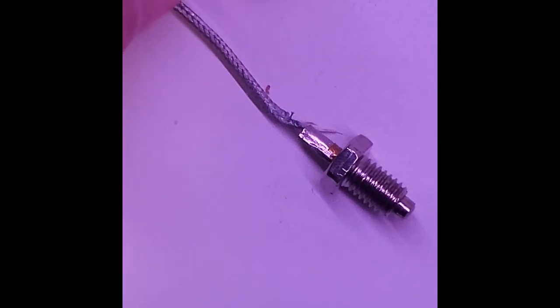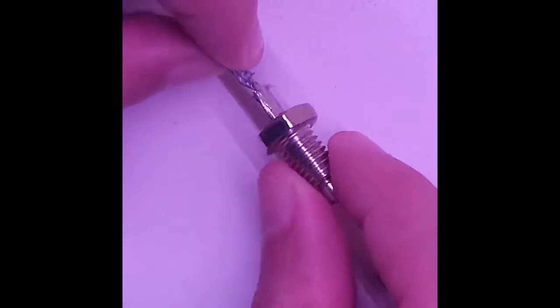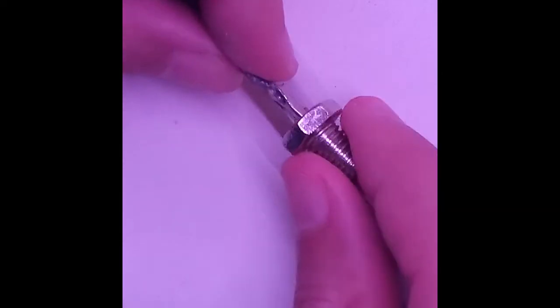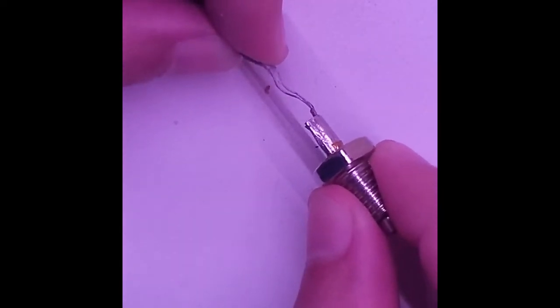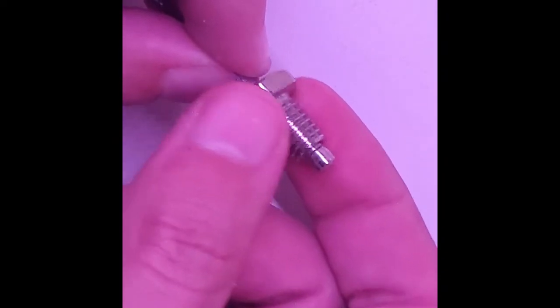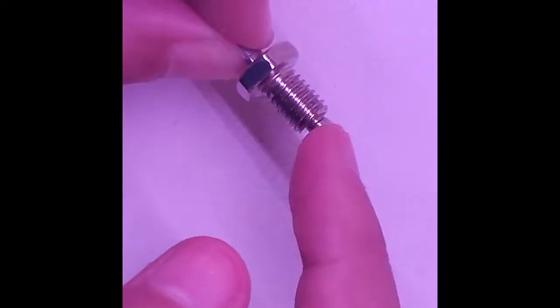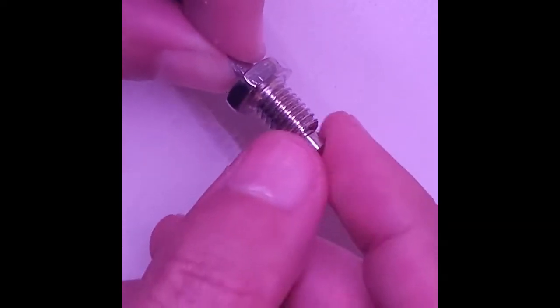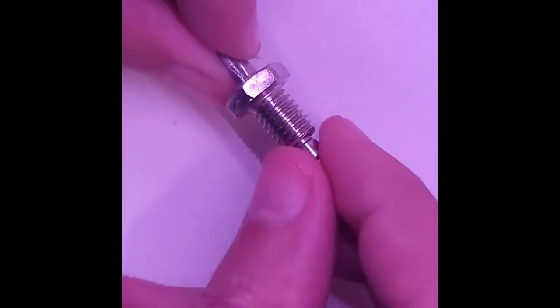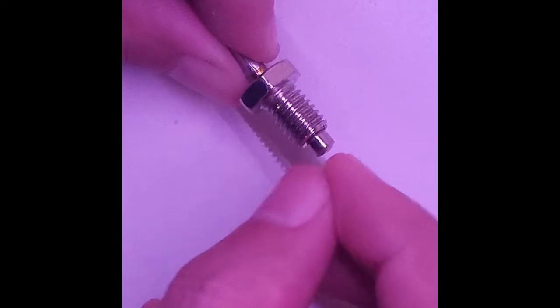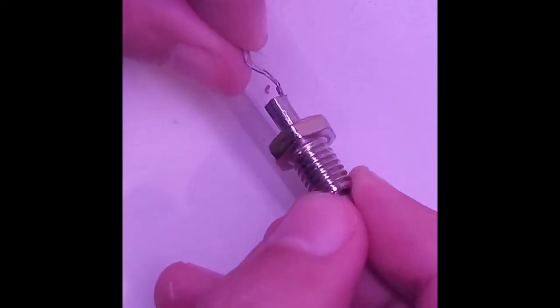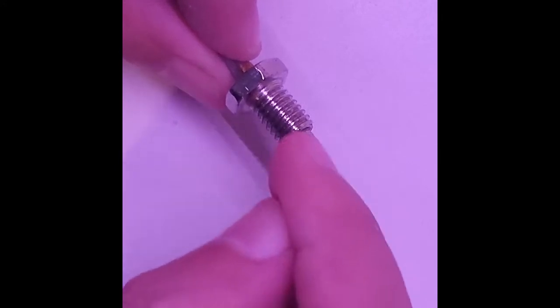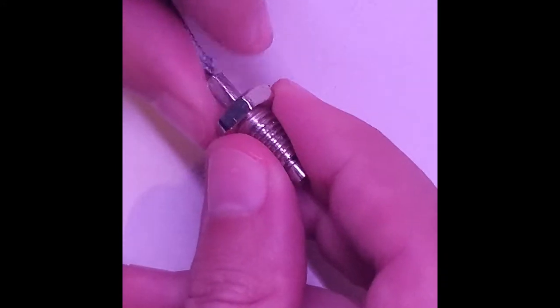Another thing to note that's important is that these thermocouples come in this casing. There's actually the thermocouple—the two wires soldered together—and they fit inside this hollow tube. Then there's this threaded component that slides over it. The problem is that there's an air gap between this outer casing and the thermocouple inside, so you don't get an accurate temperature reading because the heat takes a long time to warm up this thermocouple, or may not warm it up to the actual temperature that this casing is in contact with.